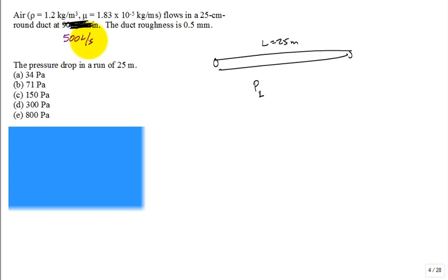All right, well, how do you calculate that pressure loss? You unravel the definition of the friction factor. Friction factor, Reynolds number, that's the Moody diagram. And so you're jumping around getting that friction factor. Once you have the friction factor, you know the length of the pipe, the diameter of the pipe, and the velocity pressure, you can calculate the pressure loss.